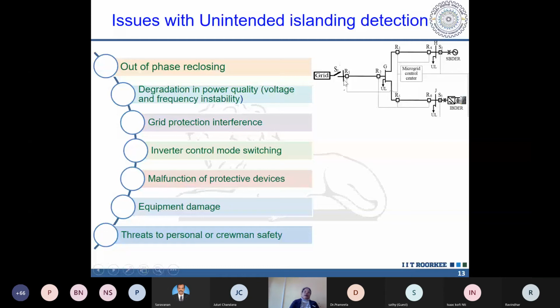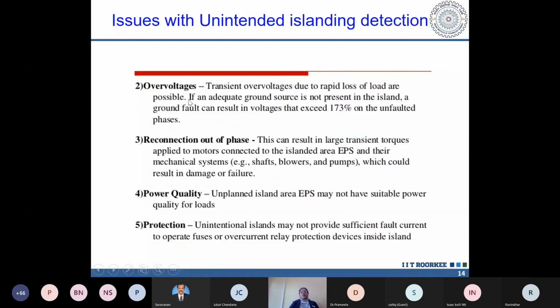And over that, I'll tell you another point. Overvoltage may also occur due to transients. Overvoltage may rise due to a rapid loss of loads. And if you don't have an adequate grounding system, meaning a ground source is not present in the island, a ground fault can result in a voltage exceeding 173% on the unfaulted phases. So these overvoltages are also a serious issue. On this topic, some people can also go ahead and research. We are also trying to investigate more, not in a theoretical aspect, but in a very practical aspect. Okay, so these are some of the power quality issues already said.